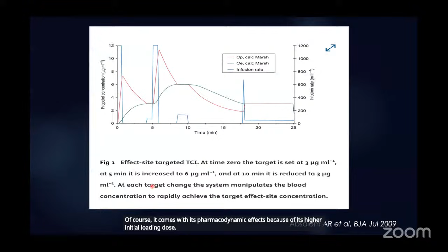So let's see how the pump works that out. As an example, when we are using an effect site targeted target control infusion, at time 0, we decide that we want a concentration of 3 at the effect site. So what the pump will do, which is the blue line, is it will give a sharp high bolus and it will stop bolusing. Now this will cause an increase in the plasma concentration, which is the red line, causing the drug to move into the brain because of the concentration gradient. And as the effect site concentration increases and matches the target that you've set, the plasma concentration will start dropping. Now at 5 minutes, you decide to change it to 6. So once again, the infusion pump gives a bolus. You are not delivering a bolus, you are only increasing your target. The bolus is delivered by the pump.